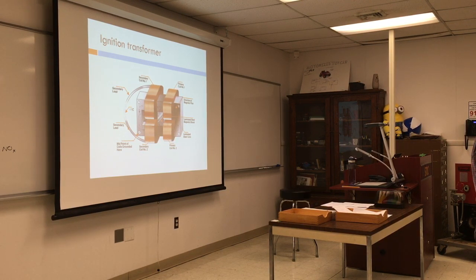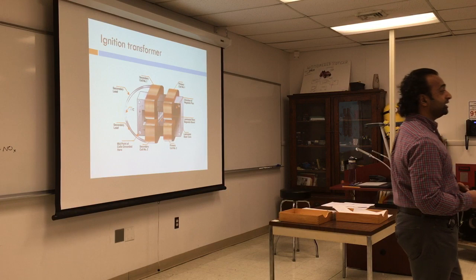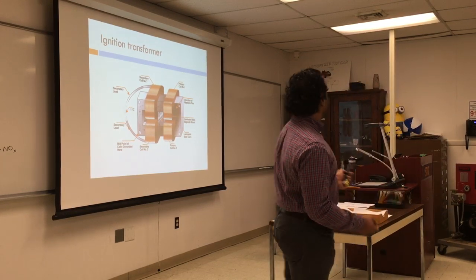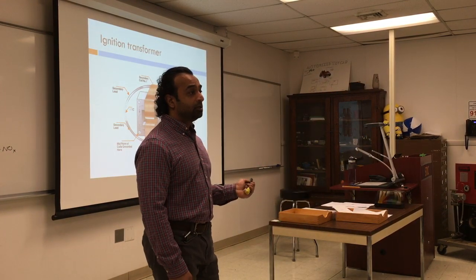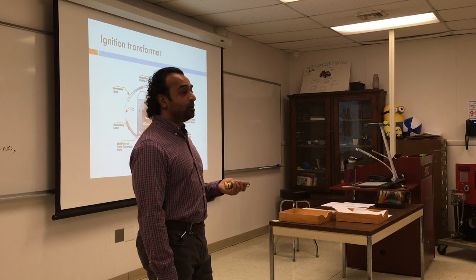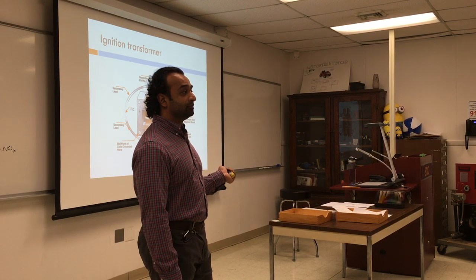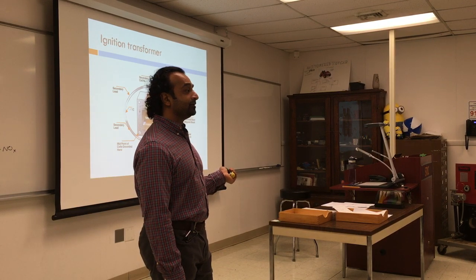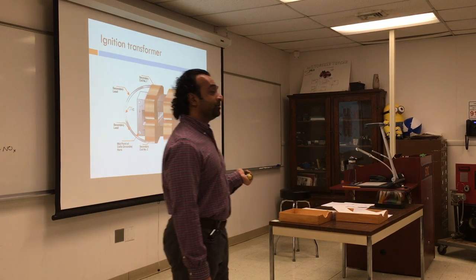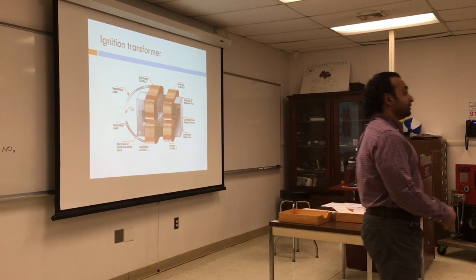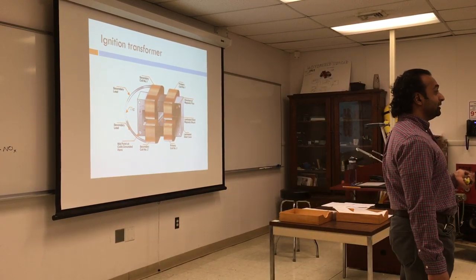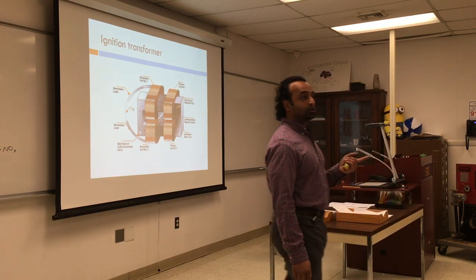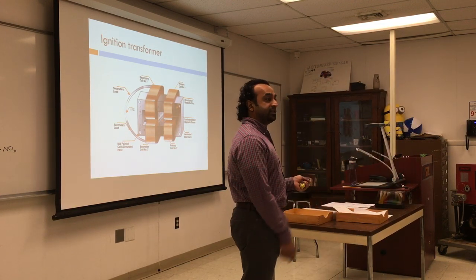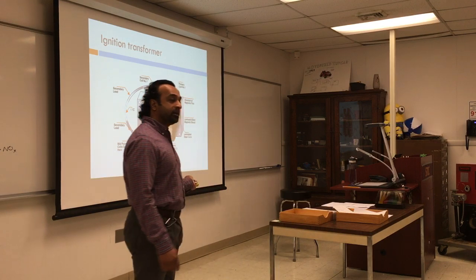Also, one of the good ways to test the transformer is to turn it on and measure the amperage. It should not drop more than 10% within 5 minutes. So again, as it heats up, let's say it was cold, then it heats up. What happens to the resistance when things are hot? Increase or decrease, Anthony? What happens to the resistance when the wire here is hot? Goes up. So it goes up, meaning the current's not going to be the same, meaning this will be a little bit weaker.